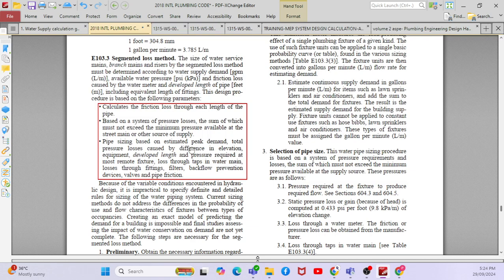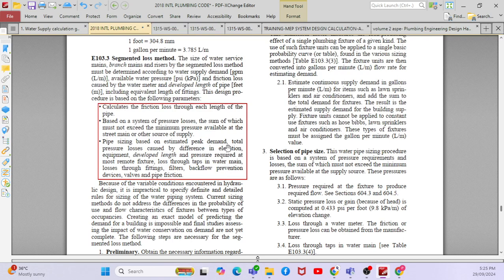Pipe sizing is based on estimated peak demand and total pressure loss caused by difference in elevation. This is an open system — not a closed system like chilled water supply — so you have to calculate the static head. You also need equipment developed length and pressure required at the most remote fixtures, including loss through taps, fittings, filter, backflow prevention devices, valves, and pipe friction.